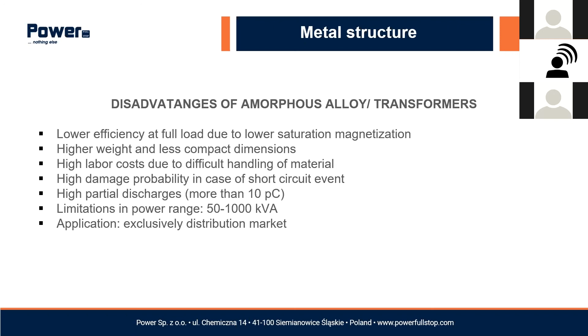There is also a problem with the short circuit test, especially because this material, when subject to short circuit, is changing its form and also its characteristics. So they discovered that there could be a big problem with partial discharges in this kind of transformer. For that reason, the power of these transformers is limited from 50 to 1000 kVA, which is typical for the distribution market.